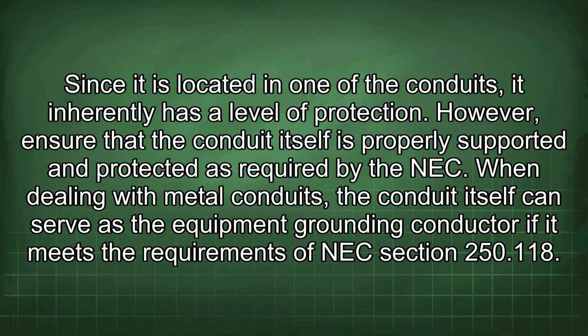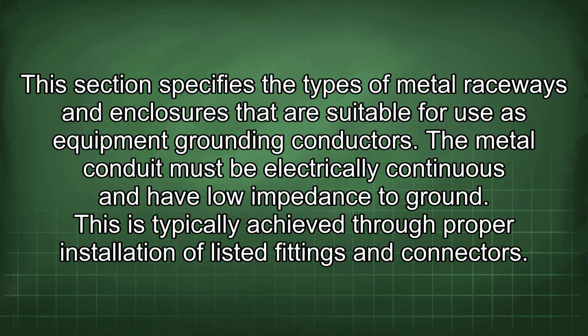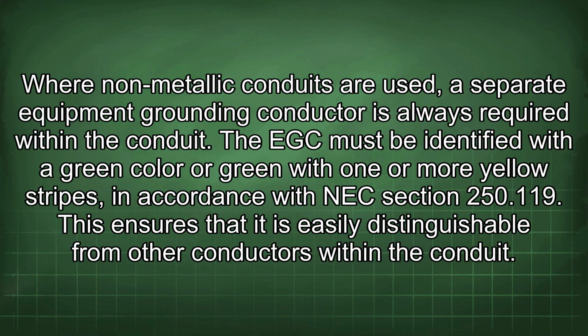When dealing with metal conduits, the conduit itself can serve as the equipment grounding conductor if it meets the requirements of NEC section 250.118. This section specifies the types of metal raceways and enclosures that are suitable for use as equipment grounding conductors. The metal conduit must be electrically continuous and have low impedance to ground. This is typically achieved through proper installation of listed fittings and connectors. Where non-metallic conduits are used, a separate equipment grounding conductor is always required within the conduit.